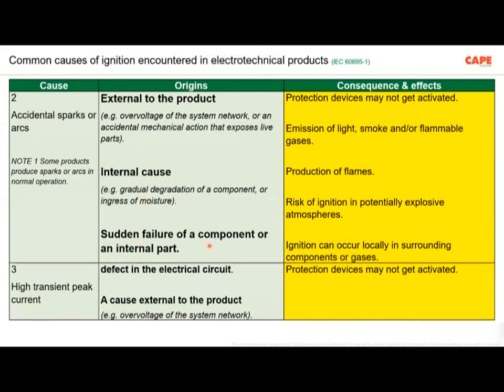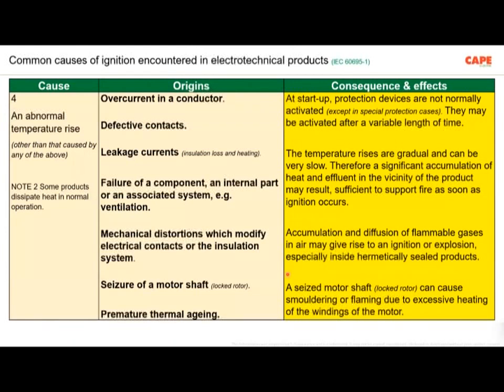Then internal causes, sudden failure of components. The consequences are written here. Protective devices may not get activated. That is always the first point of the effect. If the protective devices are not getting activated, or if the MCB didn't trip, of course we will be in trouble. The third problem is high transient peak current due to some kind of switching action, due to lightning, due to starting of a motor, due to switching of a long array of tube lights, and so on. So these also create some insulation failure where the protective device should trip and work and protect your installation.